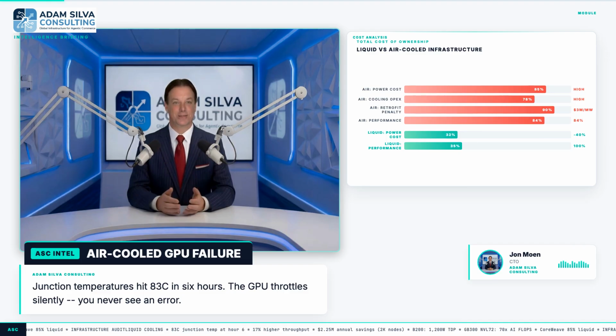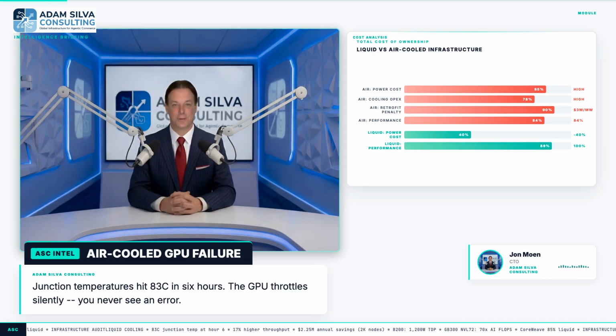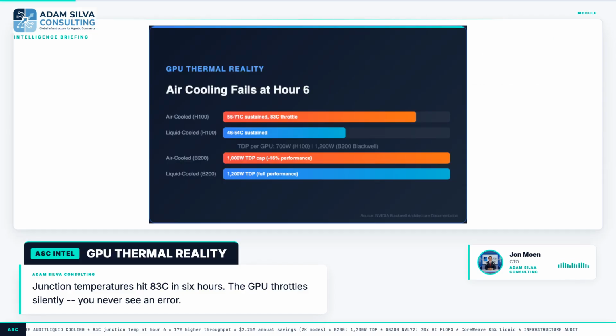I have seen this story repeat itself at 4 institutions in the last 3 years. Different vendors, different GPU generations, same route. Air cooling cannot keep pace with sustained AI workloads at the power densities modern GPUs demand. That is not a criticism of any specific OEM. It is physics, and the gap between air and liquid is only widening as TDP climbs from 700 watts on the H100 to 1200 watts on the NVIDIA B200 Blackwell in liquid-cooled config.